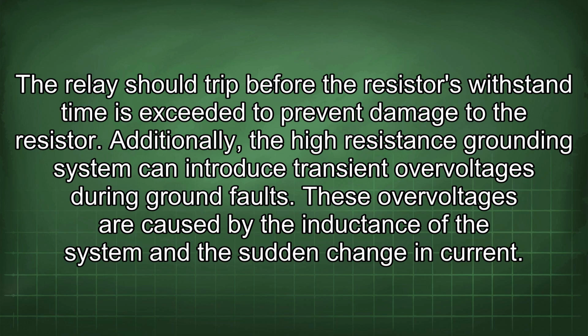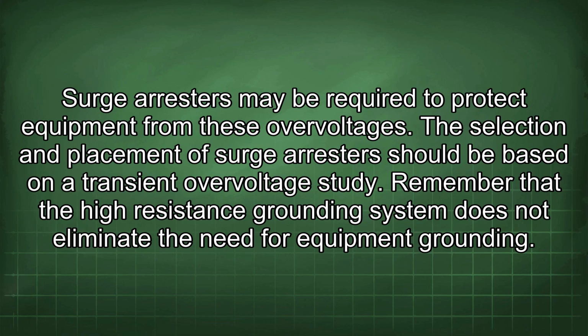Additionally, a high resistance grounding system can introduce transient overvoltages during ground faults. These overvoltages are caused by the inductance of the system and the sudden change in current. Surge arresters may be required to protect equipment from these overvoltages. The selection and placement of surge arresters should be based on a transient overvoltage study. Remember that the high resistance grounding system does not eliminate the need for equipment grounding.